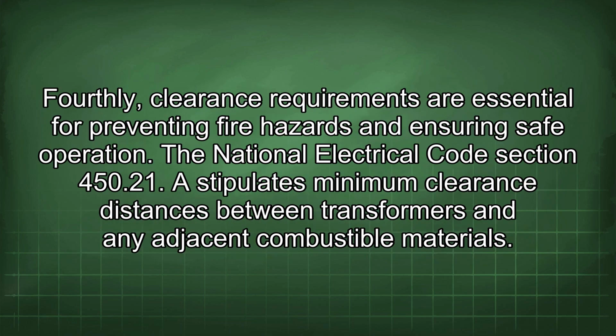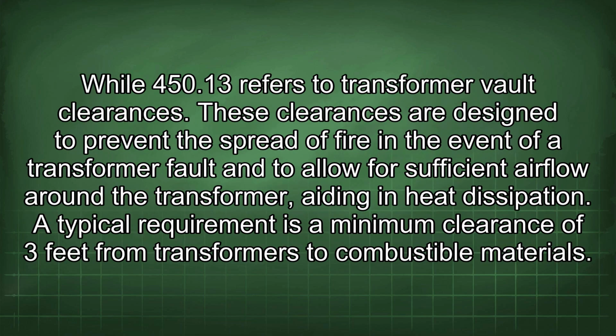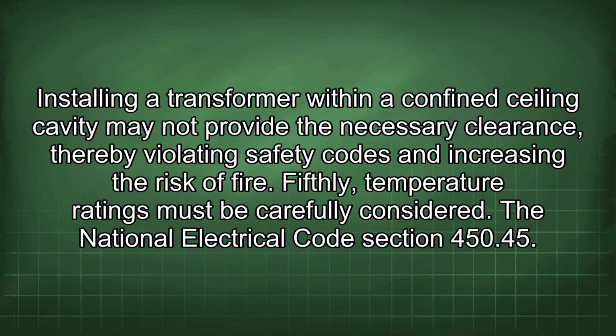Fourthly, clearance requirements are essential for preventing fire hazards and ensuring safe operation. The National Electrical Code Section 450.21 stipulates minimum clearance distances between transformers and any adjacent combustible materials, while 450.13 refers to transformer vault clearances. These clearances are designed to prevent the spread of fire in the event of a transformer fault and to allow for sufficient airflow around the transformer, aiding in heat dissipation. A typical requirement is a minimum clearance of 3 feet from transformers to combustible materials. Installing a transformer within a confined ceiling cavity may not provide the necessary clearance, thereby violating safety codes and increasing the risk of fire.